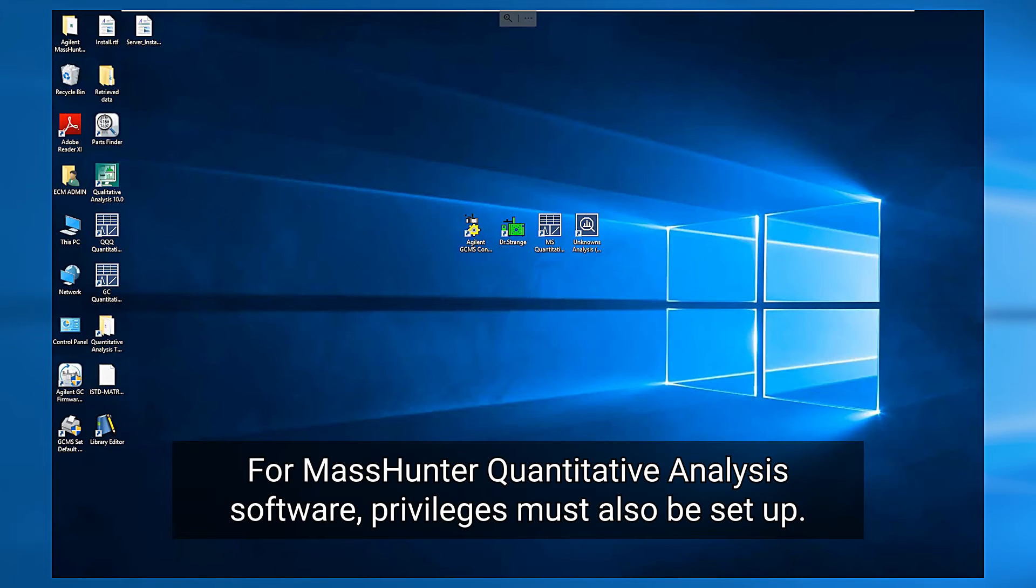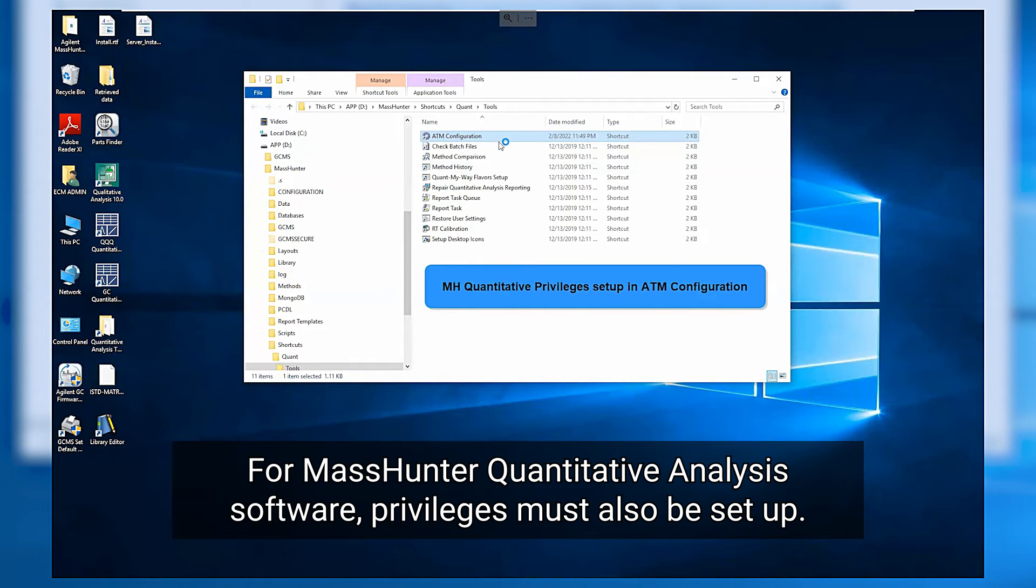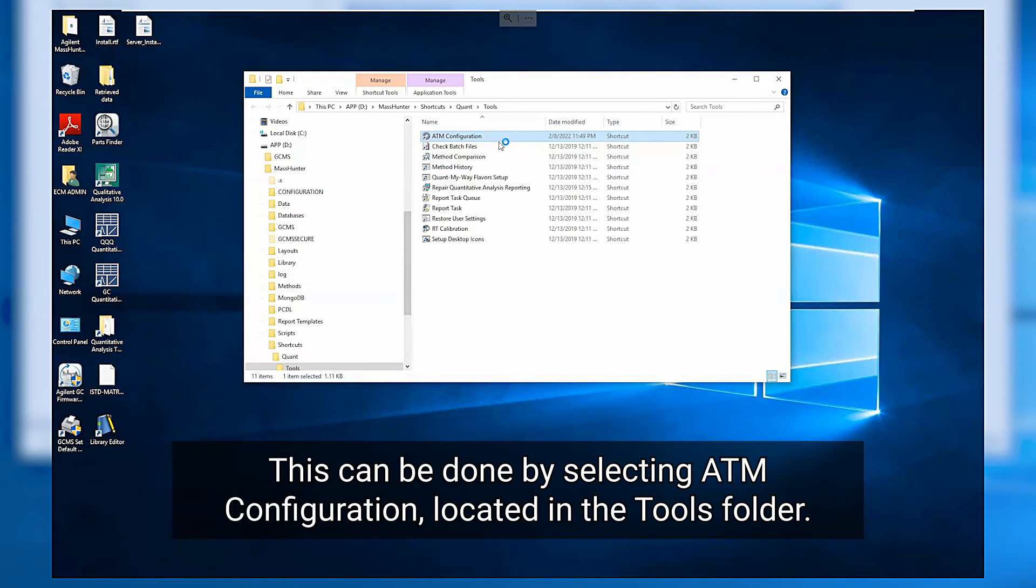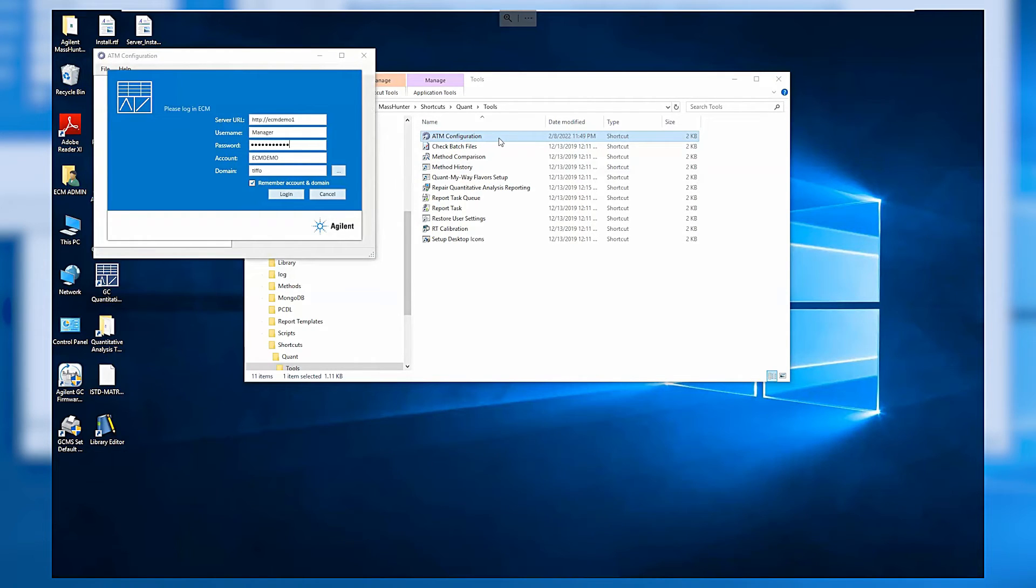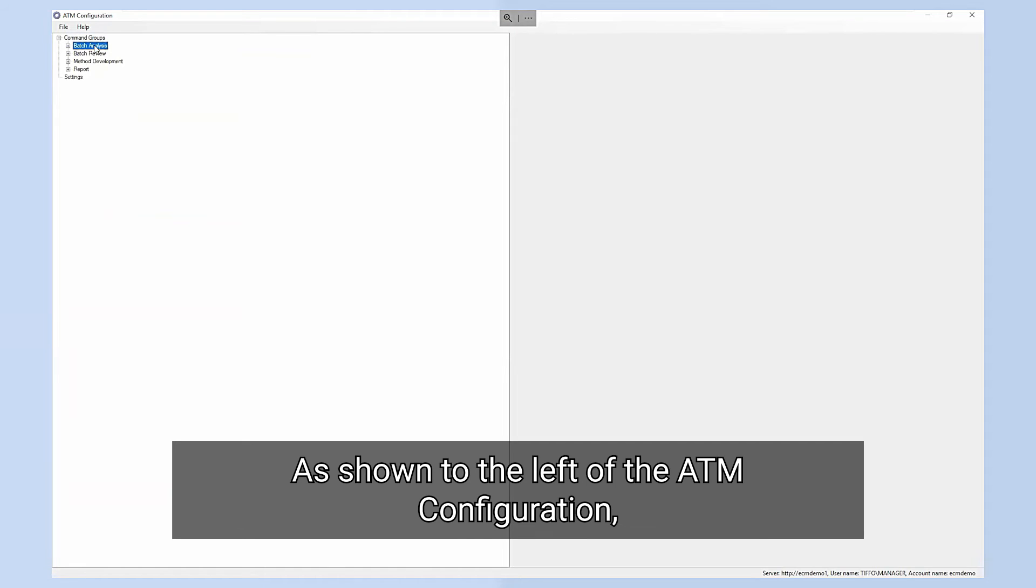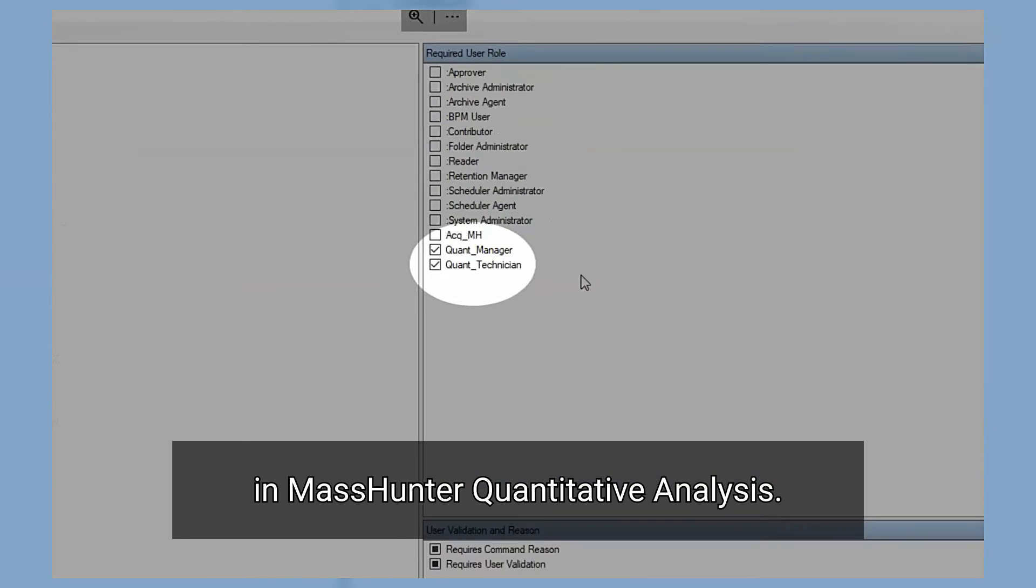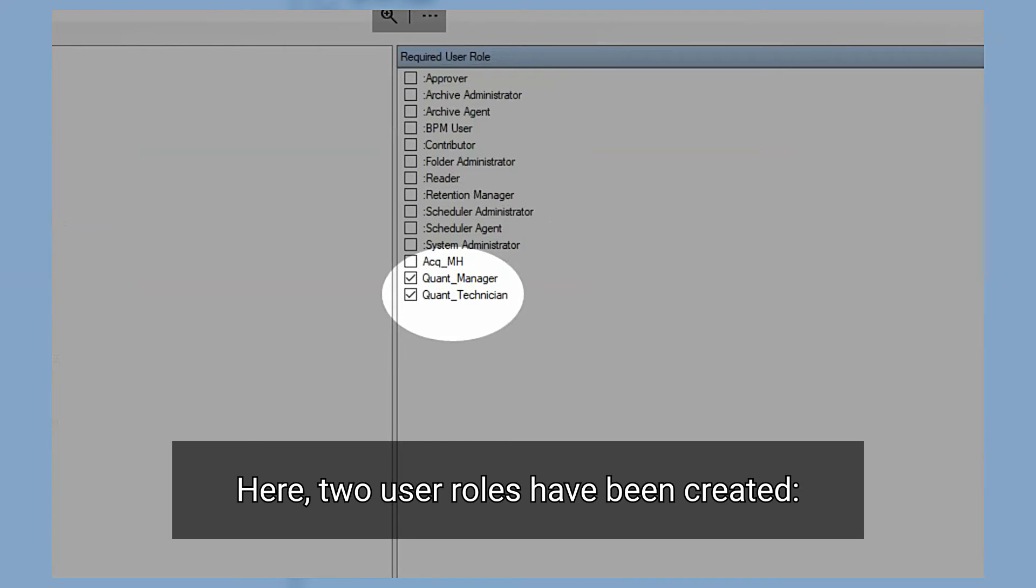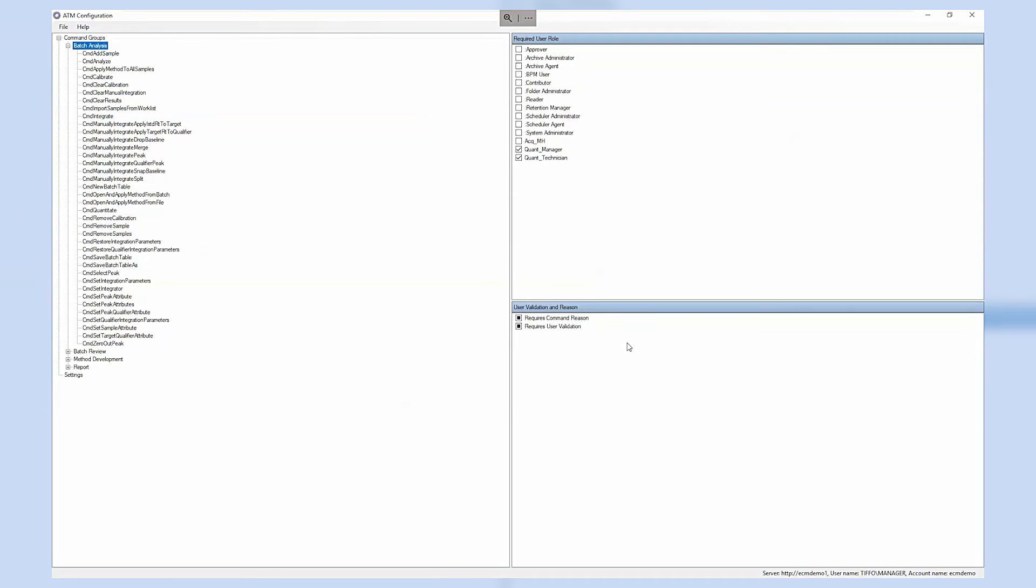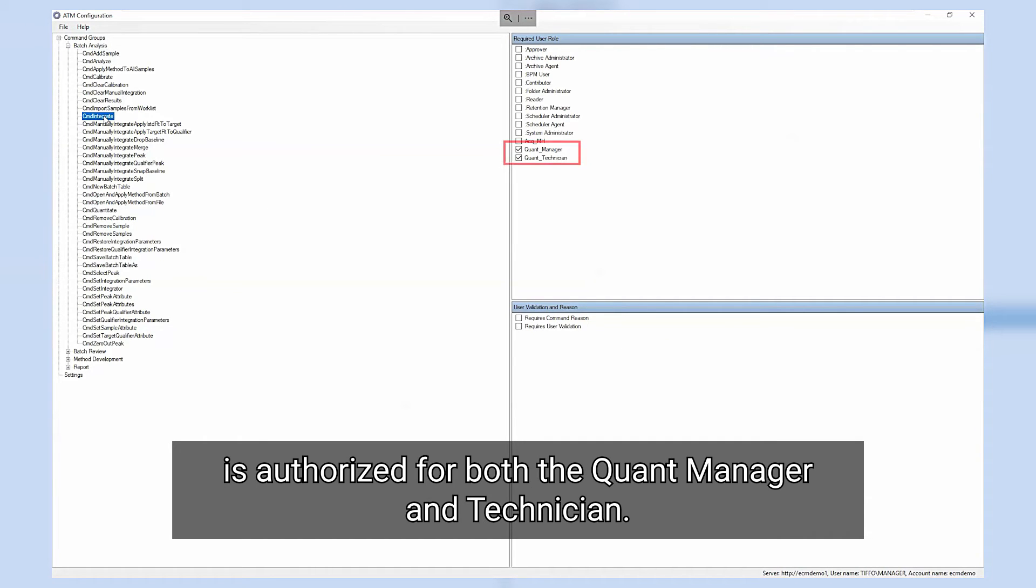For MassHunter quantitative analysis software, privileges must also be set up. This can be done by selecting ATM configuration located in the tools folder. Again users must log in as the manager to be able to modify the default privileges. As shown to the left of the ATM configuration, privileges can be given for almost every command in MassHunter quantitative analysis. Here two user roles have been created: a quant manager and a quant technician. As an example the integrate function shown here is authorized for both the quant manager and technician.